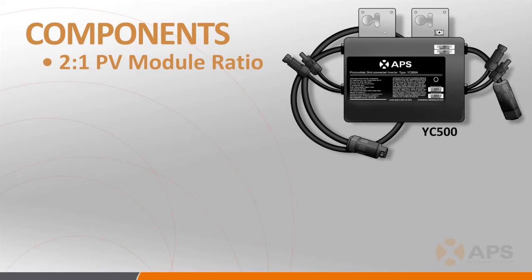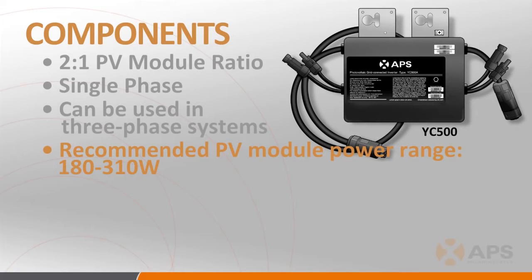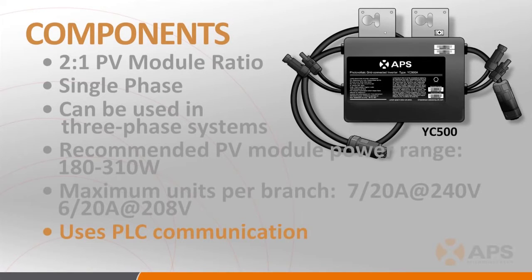The APS YC500 functions as two inverters built into a single case and has the following characteristics. It's a single-phase inverter, but given its architectural flexibility, it can also be used in both 208-volt and 277-480 3-phase applications. It is best suited for PV modules in the 180-310 watt range, and its total rated output power is 500 watts. The maximum number of units per 120-240 volt, 20-amp circuit is 7, or a total of 14 PV modules, and the maximum number of units per a 208-volt, 20-amp circuit is 6, or a total of 12 PV modules. The YC500 uses the Powerline Communication, or PLC, protocol to communicate with the ECU, and while the warranty varies depending on pricing, it has been engineered for a design life of 25 years.